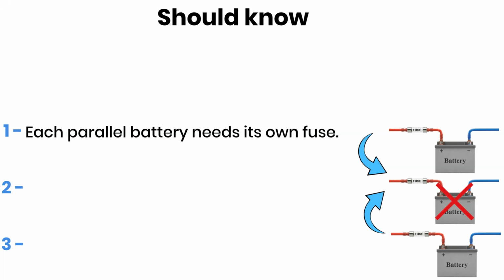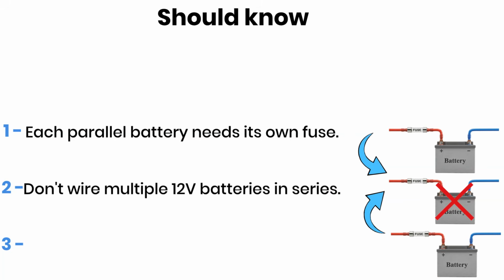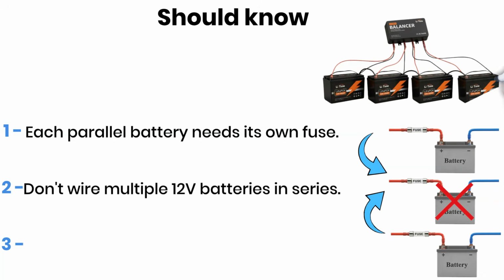The second point is for anyone building a 24-volt or 48-volt battery system. Whenever possible, use batteries that are already designed for your system voltage. For example, if you're building a 48-volt system, choose 48-volt batteries instead of connecting several 12-volt batteries in series. The reason is simple. When batteries are connected in series, they don't automatically stay balanced with each other. Over time, differences between the batteries can grow, which often means you'll need battery balancers or additional equipment to keep everything operating correctly. Parallel batteries behave differently. Because they're connected directly together, they naturally equalize their voltage, making the system much simpler to manage. That's one reason many installers prefer parallel battery banks whenever it's practical.